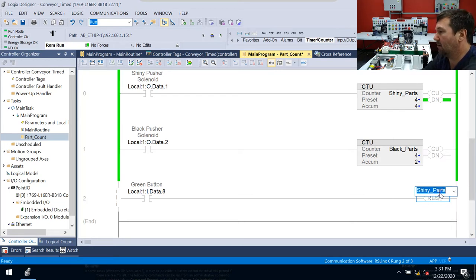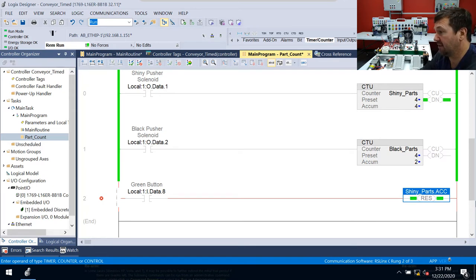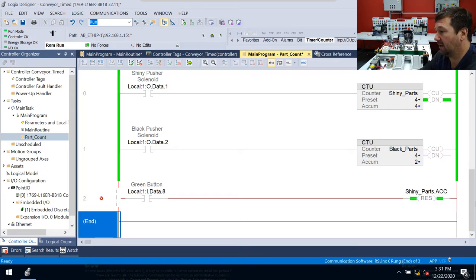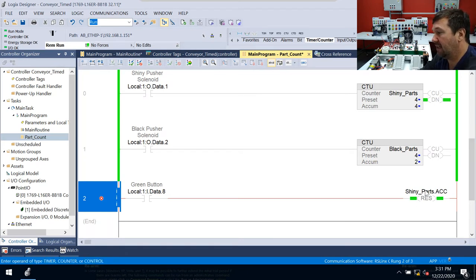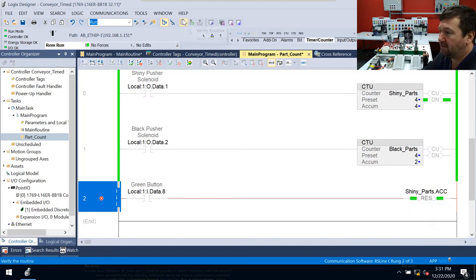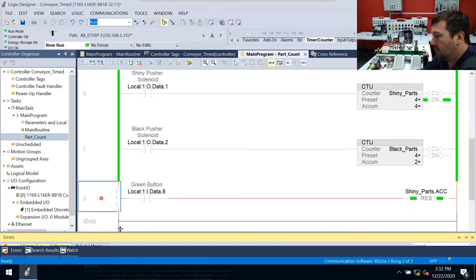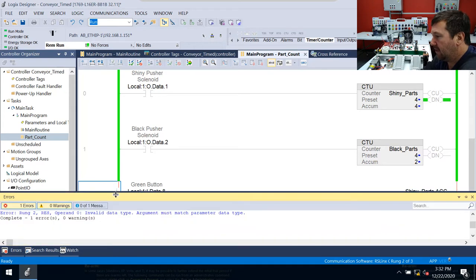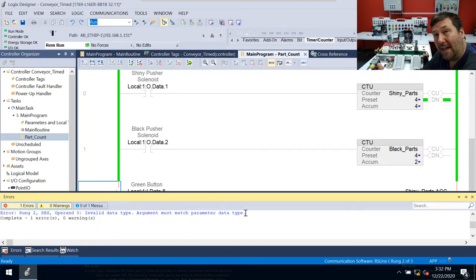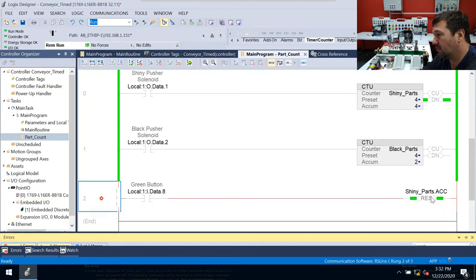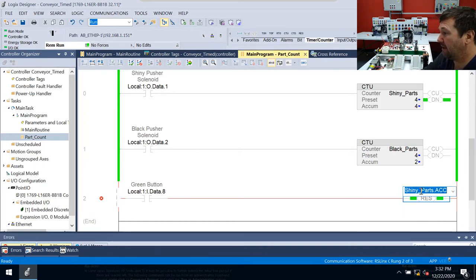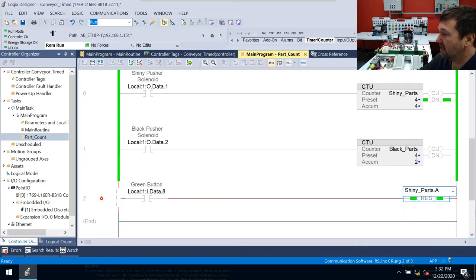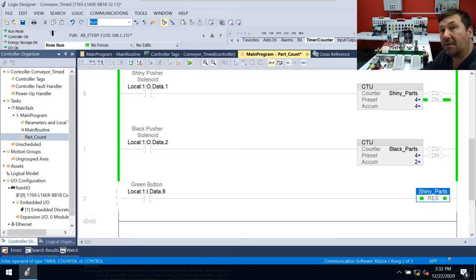And we're going to reset the counter. So a lot of people will want to say, well, I want to reset the ACC. Because really, that's all we care about. Let's reset the ACC. Well, when I go off this rung, you're going to see it stays red. And it's because in the case of these, you reset the entire counter structure. So let's hit the verify routine button so we can see that. We'll drag our error tab back up. It says here, invalid data type argument must match parameter data type. Which can be a little vague if you don't know a lot about data types yet. But for now, let's make sure that mainly we know if it's a reset, usually you're going to reset the entire structure. So if we just put in shiny parts, and we go off of it, our red X is gone.